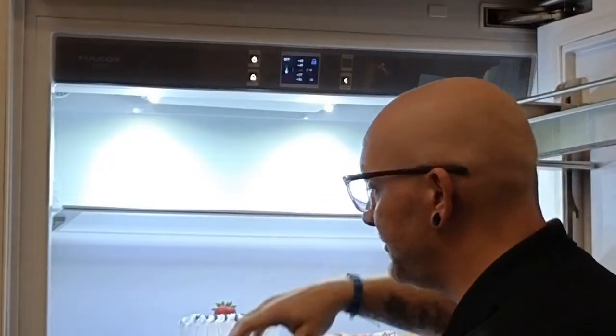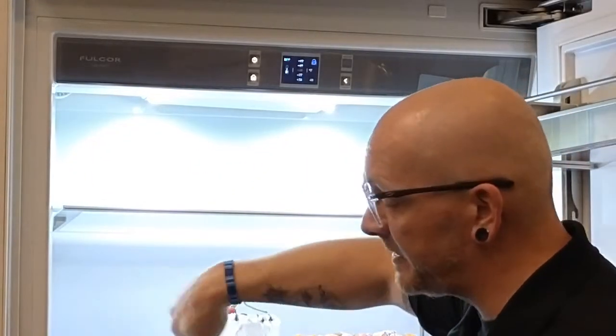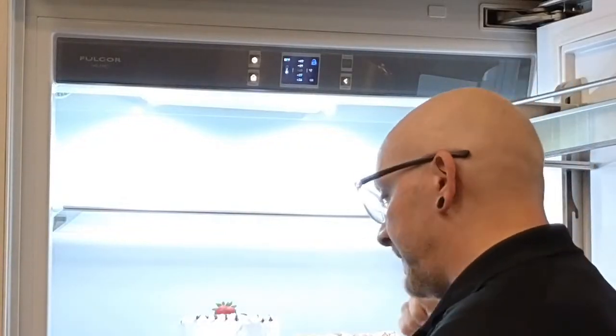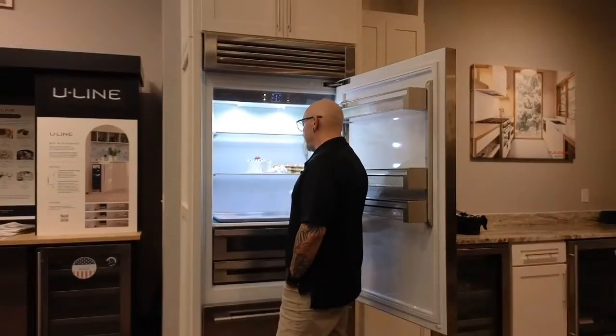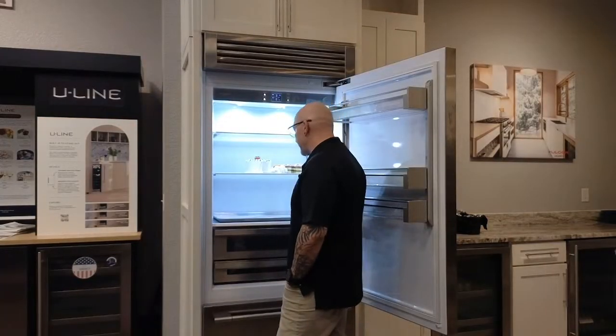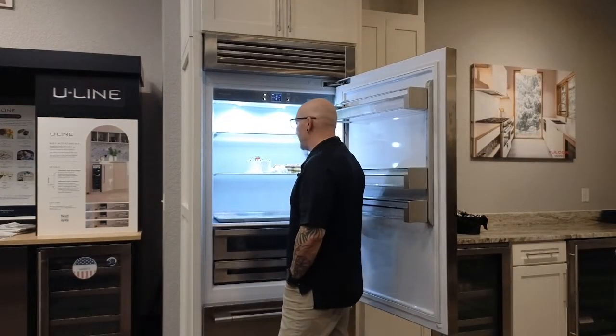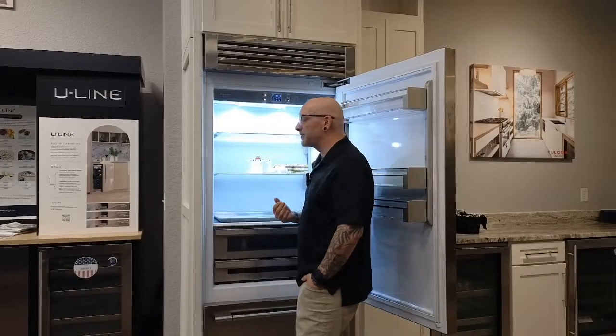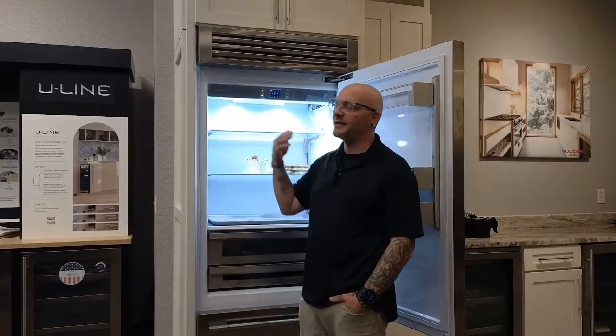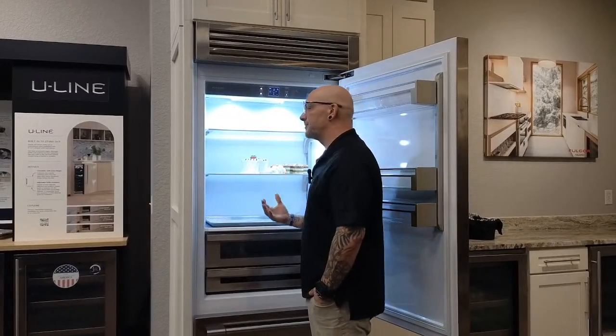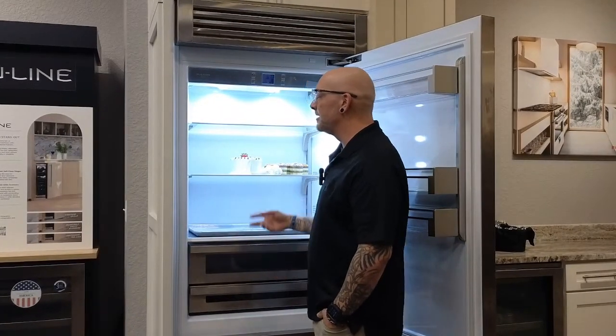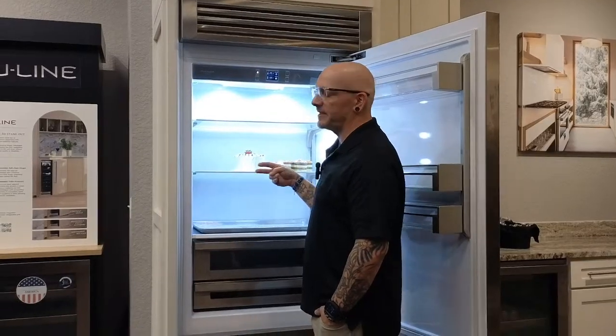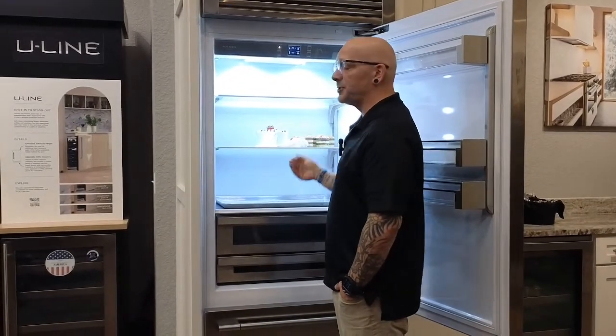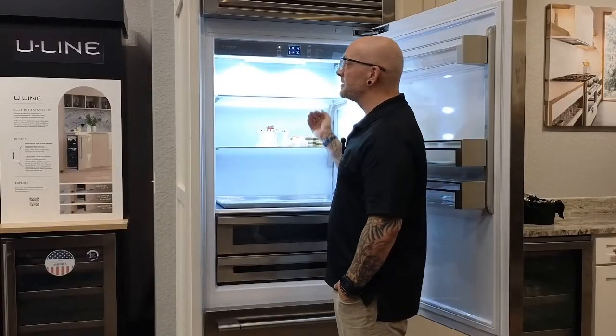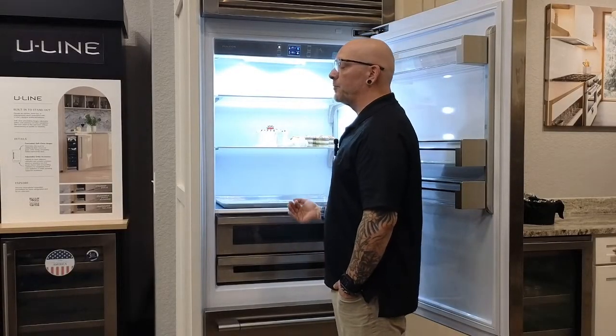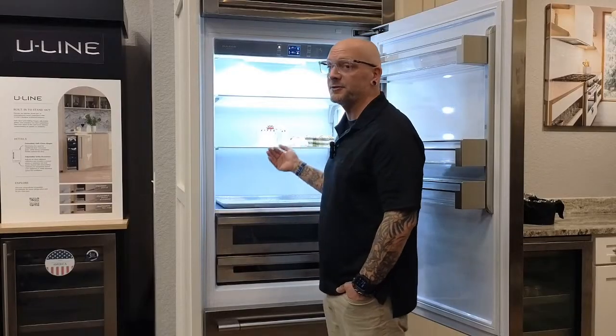The one issue that I do notice is the vents on the right side or the left side, depending on which refrigerator you have. I love to stick my milk and my big jugs of iced tea and different things right in front of those vents, and I have to remind myself, don't block your vents. So remember to always remind your customer, don't block the vents. It's going to block airflow and cause cooling issues between the two sections, because although they are two separate sections with two separate compressors, they share a condenser. So if one section is struggling, the condenser will be warmer than necessary, which will cause the other section to start to struggle as well.